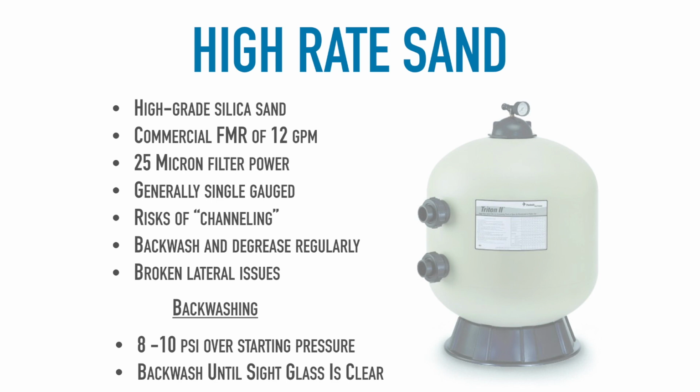And instead of my water going through the sand bed, instead it's going to run on the outside of the sand bed. This is called channeling. Now, if I were you, I would write down that channeling equals unfiltered water back to the pool. Channeling equals unfiltered water back to the pool. We don't want unfiltered water going back into our pools. So this is why we need to make sure that we're backwashing and degreasing regularly.